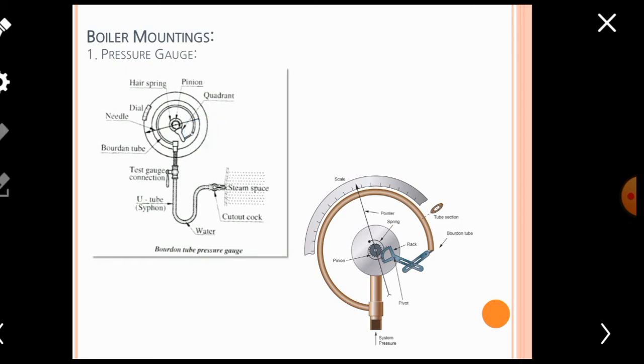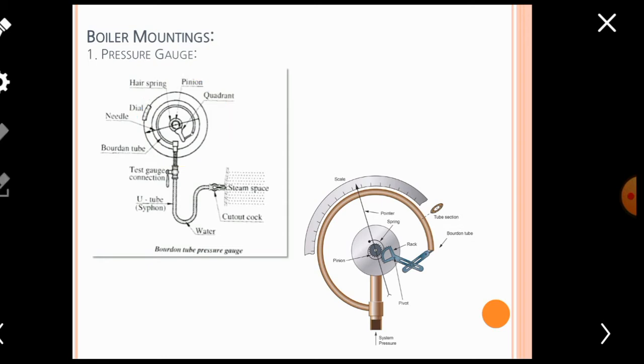This rack or quadrant is connected with a central gear known as a pinion, which is centrally mounted on a spindle. At the top of the spindle a pointer is connected. The entire assembly or mechanism is enclosed in a closed body called the dial body or pressure gauge body. At the front there is a glass cover, and exactly below that glass cover there is a circular dial with graduated pressure units.